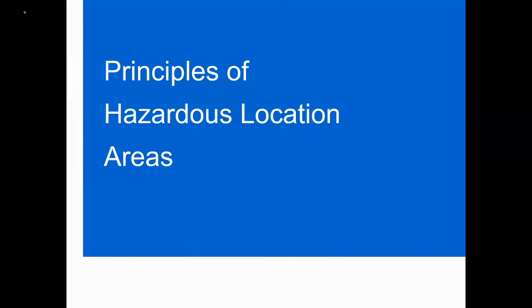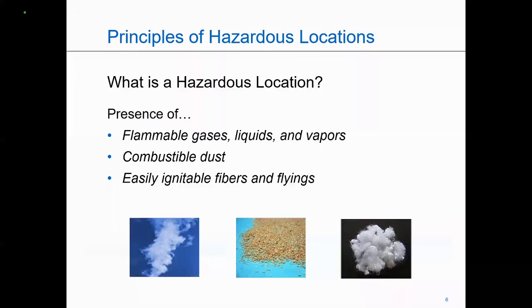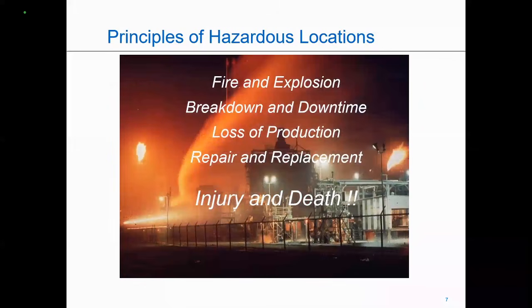So right from the basics, what is a hazardous area? A hazardous area is an area where the presence of flammable gases, liquids, and vapors, combustible dust, or easily ignitable fibers and flyings can cause fire and explosion, breakdown and downtime, loss of production, repair and replacement, injury and death. Obviously, the last one is the worst case scenario. We really want to avoid any injuries at all.